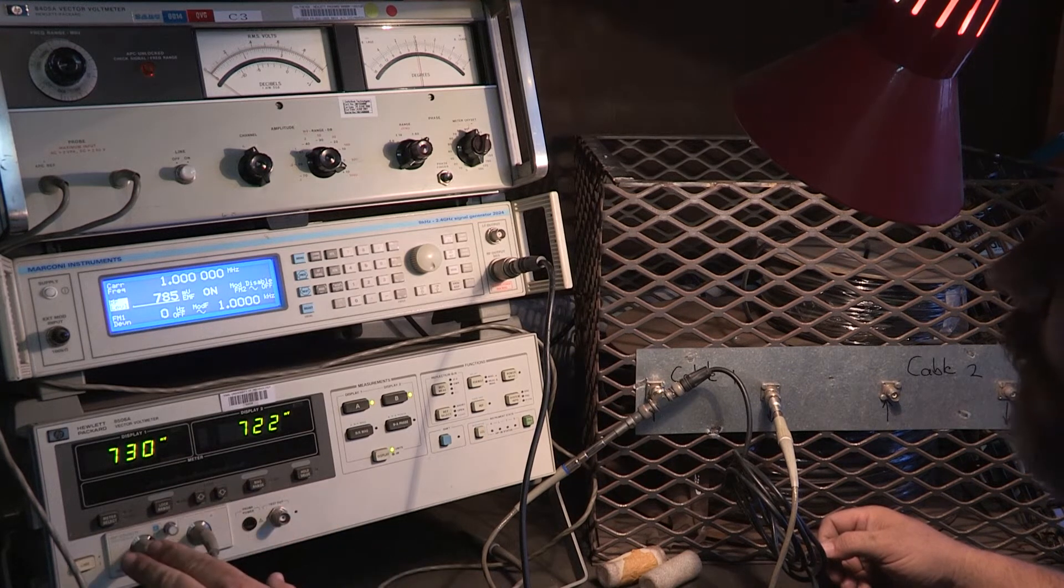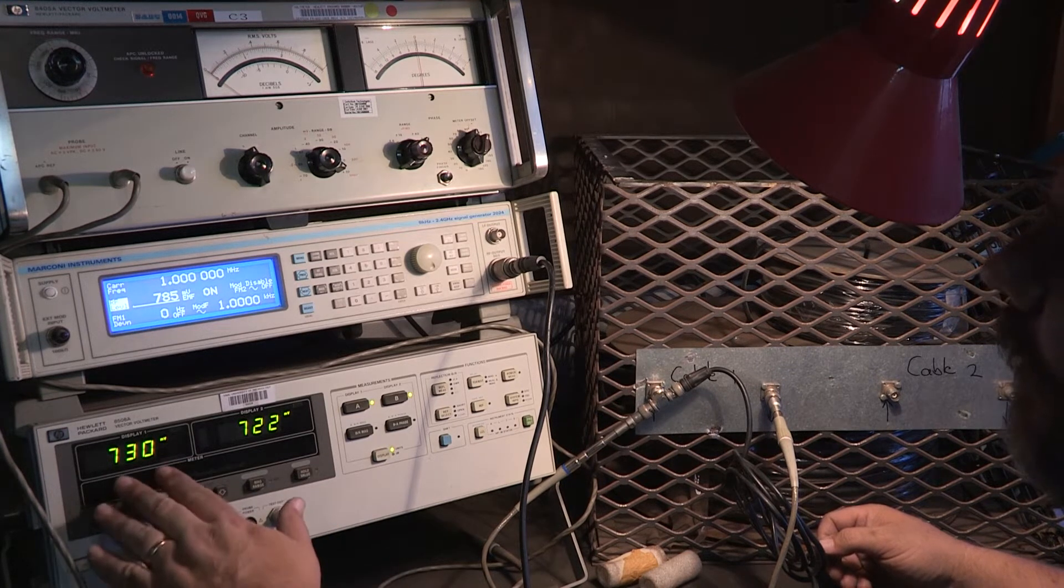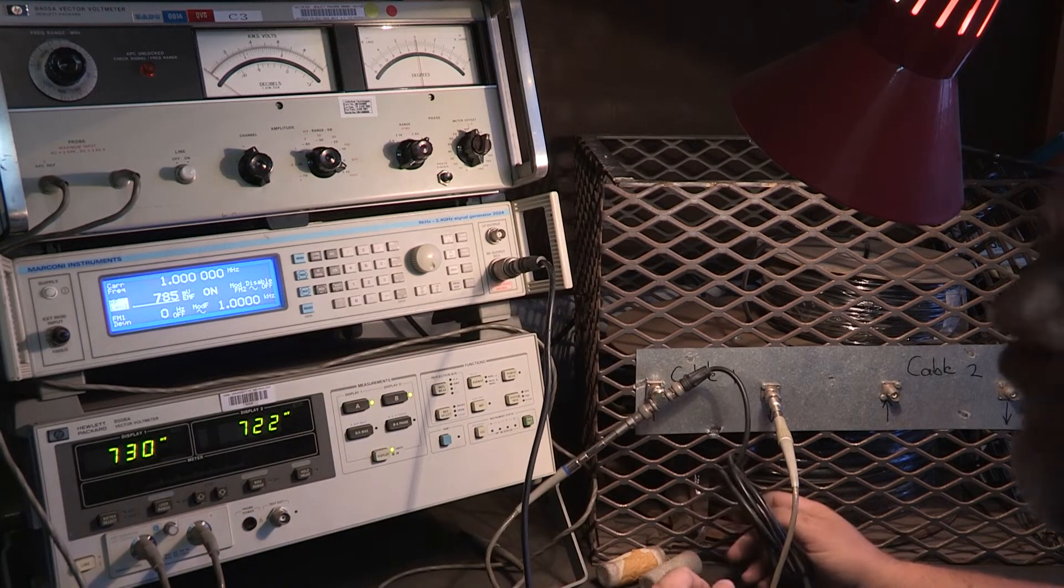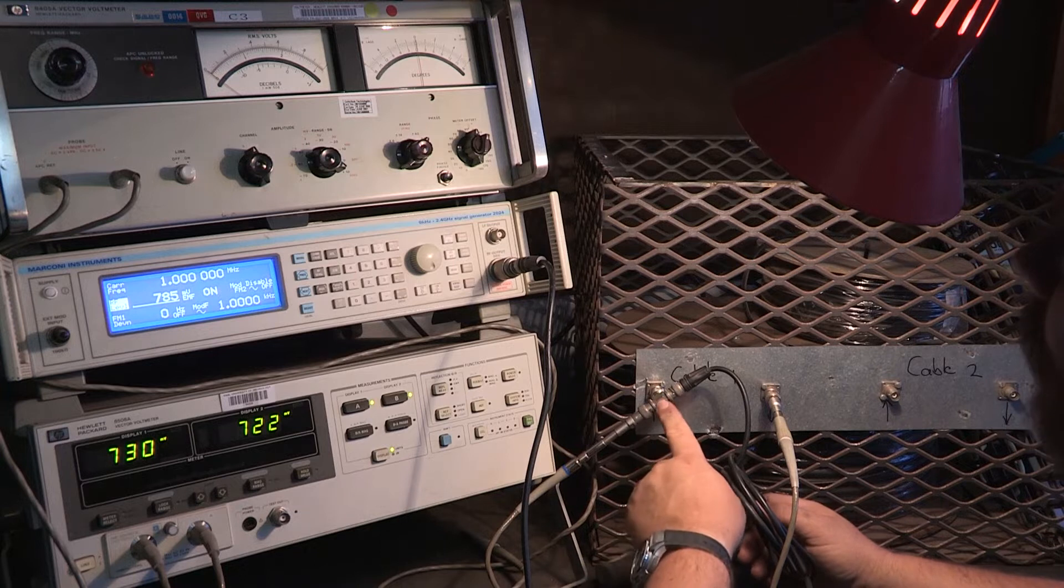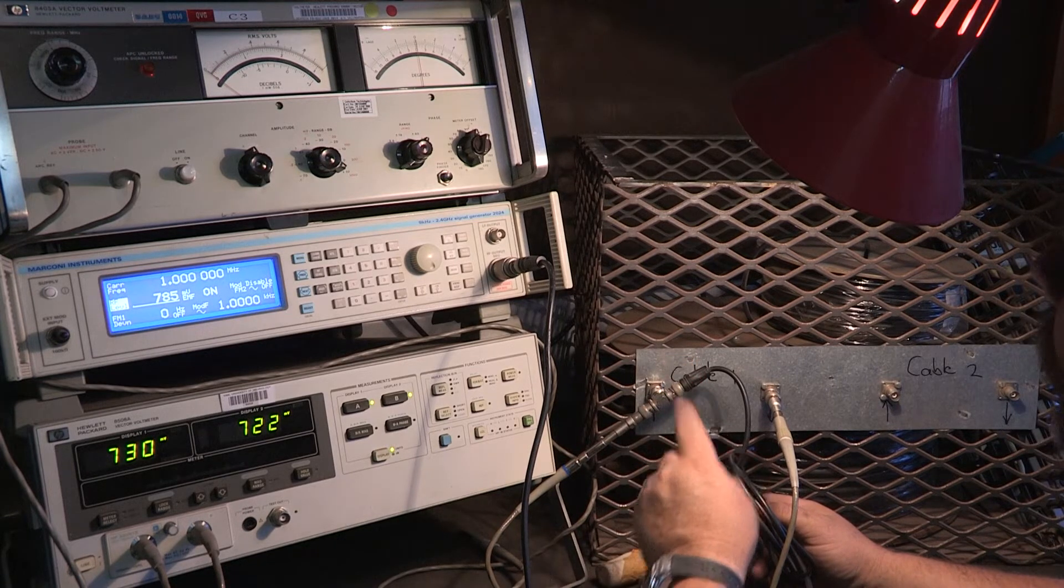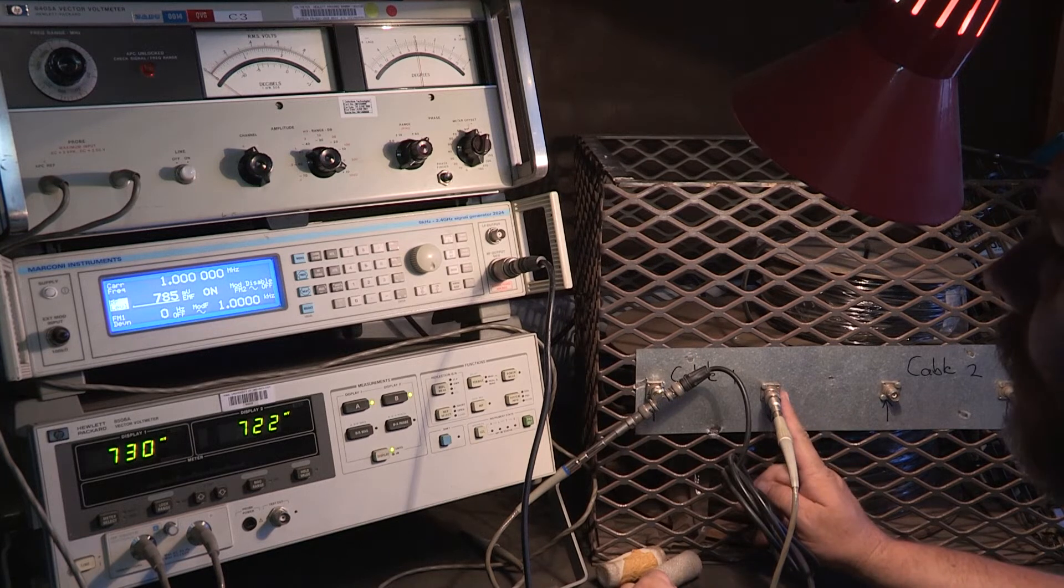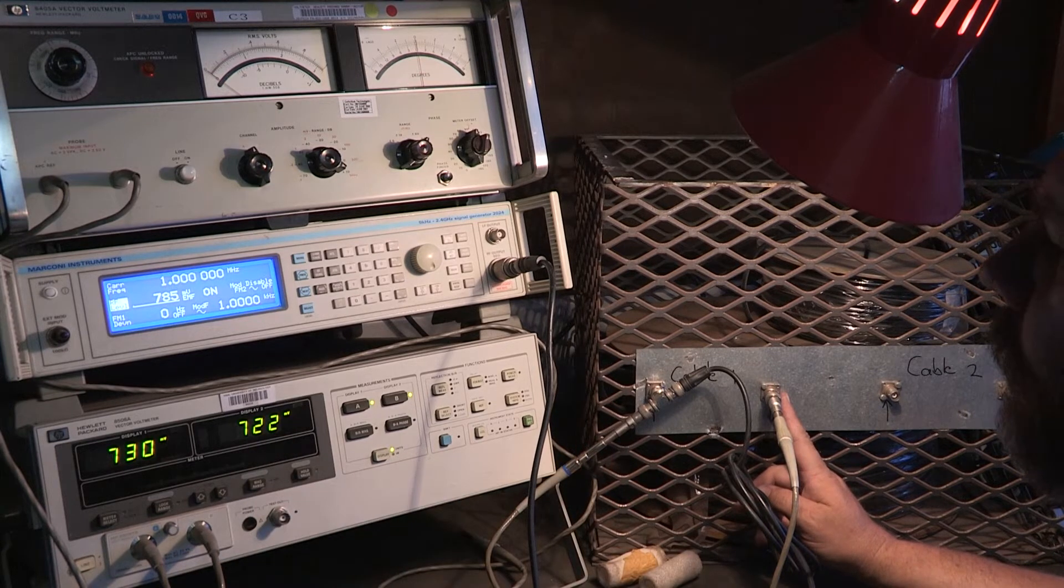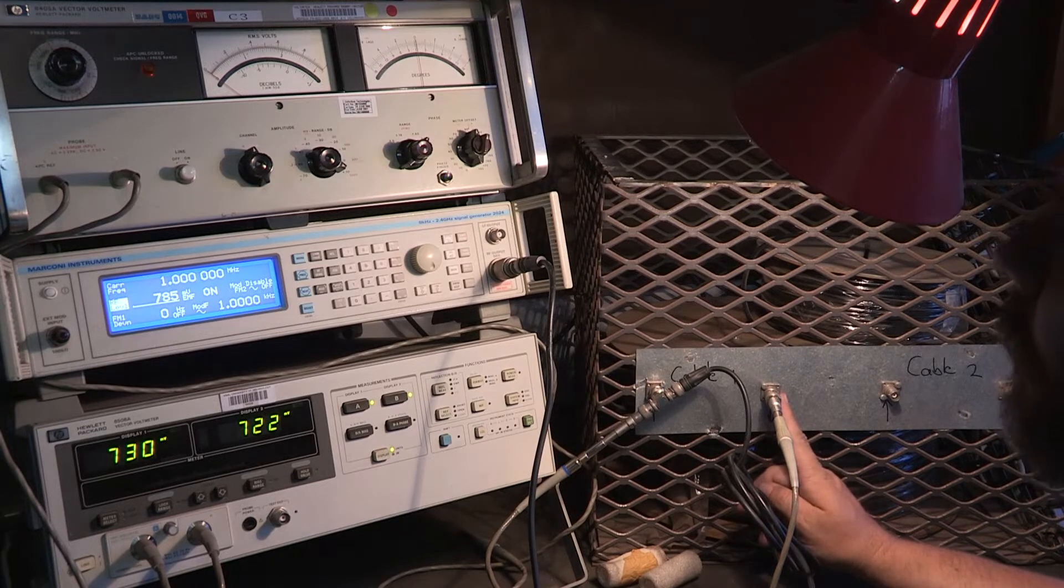On the display of the vector voltmeter, we have channel A and channel B. Channel A gives me, after my feed line and everything else, the voltage going into the cable. And as a result, going out of the cable on channel B, I can simultaneously see the output cable voltage.